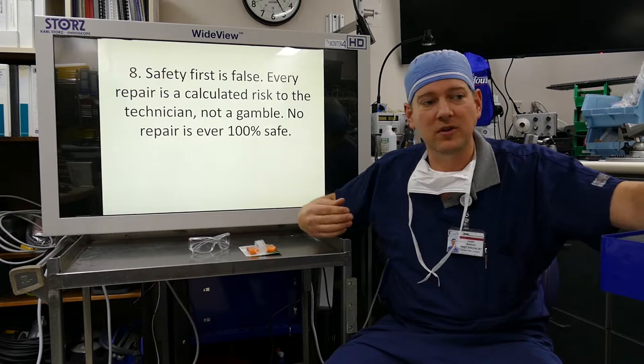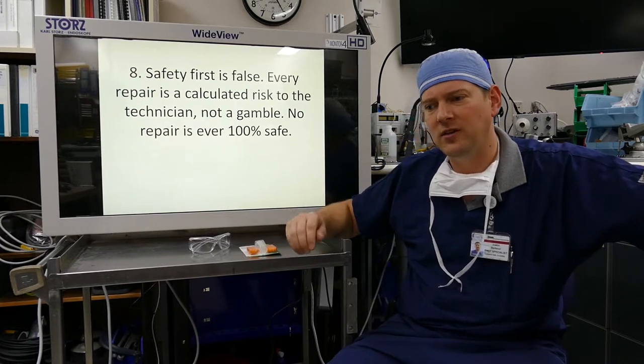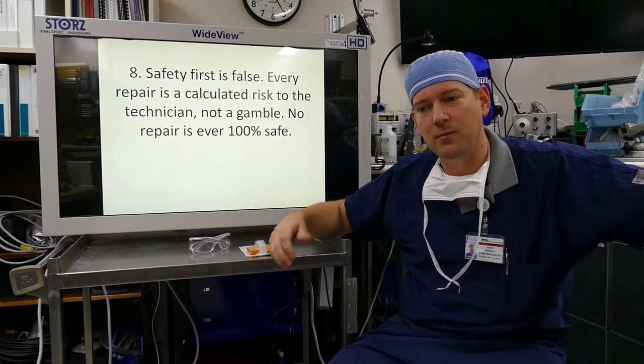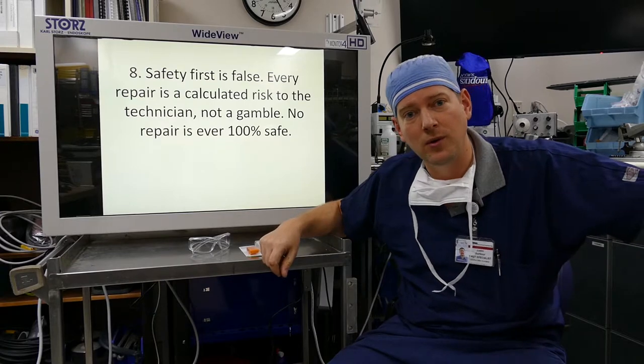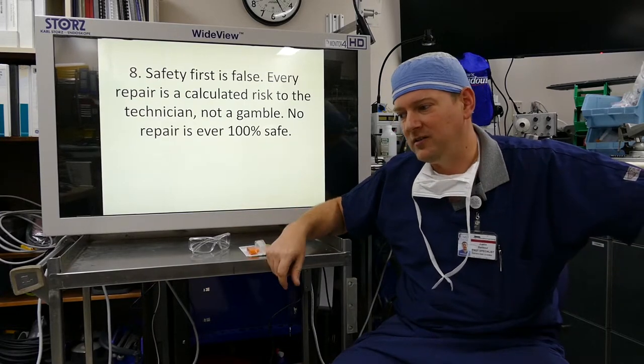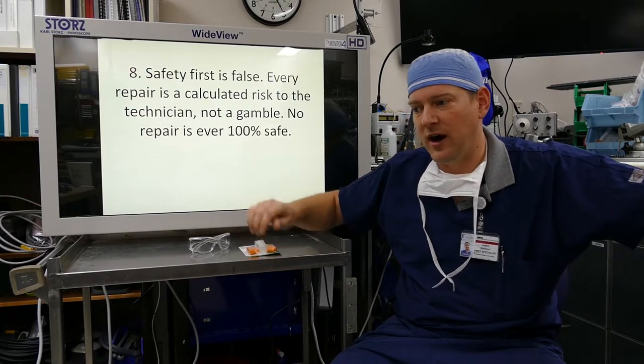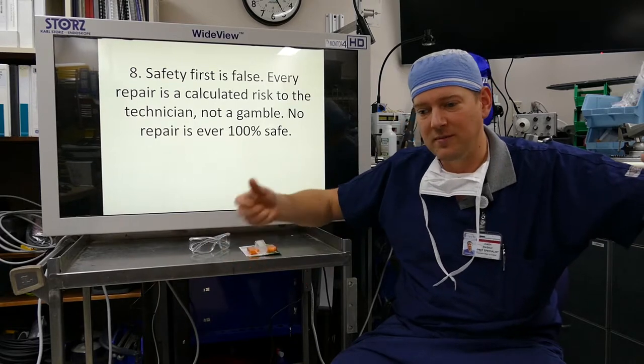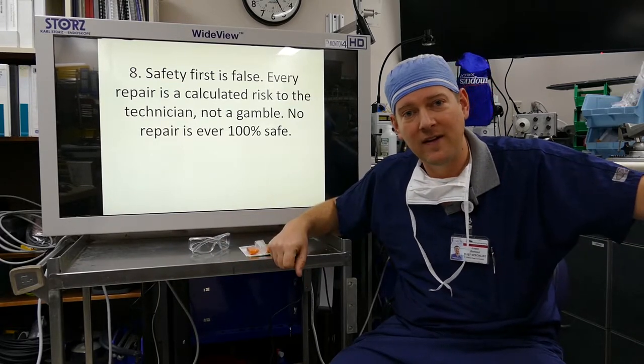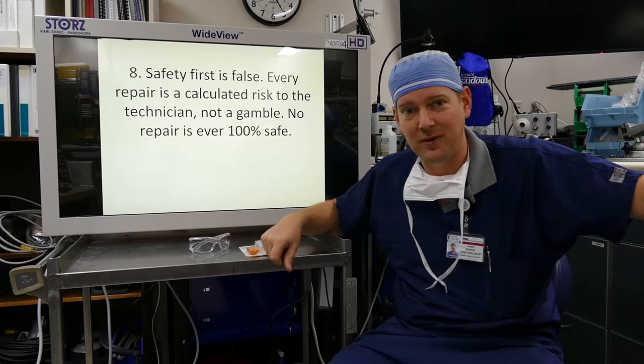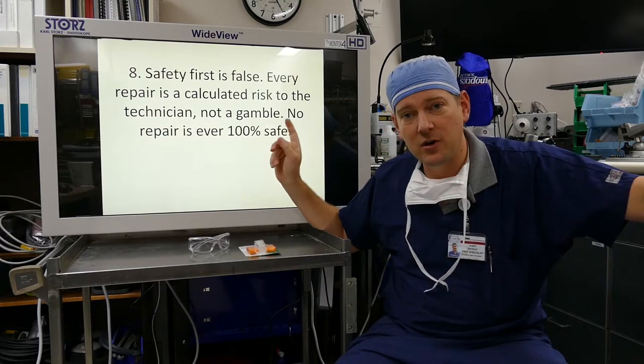Sometimes it was my fault, but sometimes it's not my fault. How do you know there's a fray of wires underneath the lip when you go to lift a cover off? You don't know that. How do you know that device had an open neutral and an open ground and it was hot, and you grabbed the stainless steel case? You don't know that. The users aren't going to be that descriptive, that's for sure. No repair is 100% safe.